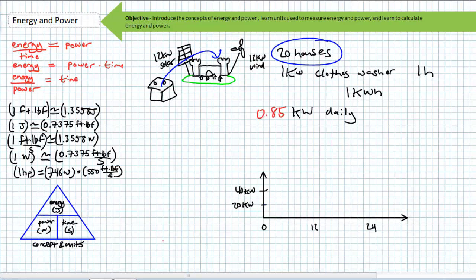Let's say all together we can reduce the energy consumption of these houses by 15%, or drop it by 150 watts each. So our constant consumption would be only 850 watts, or 0.85 kilowatts. This might seem insignificant per house, but think of the communal savings: with 20 houses, our baseload just dropped by 20 times 150, or 3 kilowatts—allowing us to purchase a smaller main genset and use less fuel when it's running.